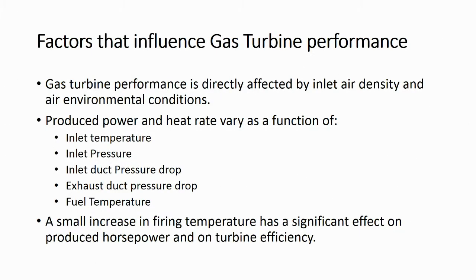Gas turbine performance is directly affected by inlet air density and air environmental conditions. Produced power and heat rate vary as a function of inlet temperature, inlet pressure, inlet duct pressure drop, exhaust duct pressure drop, and fuel temperature.